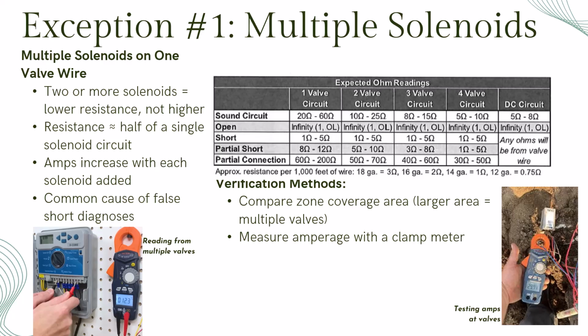One of the easiest mistakes to make in troubleshooting is misreading a low resistance as a short when in fact you're just looking at multiple solenoids on one circuit. Each solenoid gives the current another path to travel, so the total resistance drops, not rises. For example, 2 solenoids on one line may show only 10 to 25 ohms, which looks like a partial short, but it is completely normal. You can confirm this by watching the irrigation zones. If a single controller station is watering a noticeably larger area, you found your double valve circuit. Or you can measure the current. The amps will double or triple depending on how many solenoids are connected.